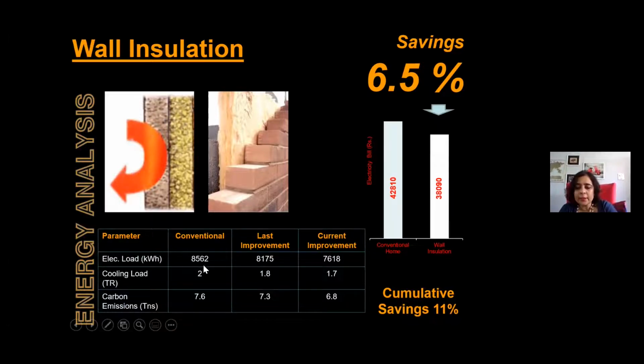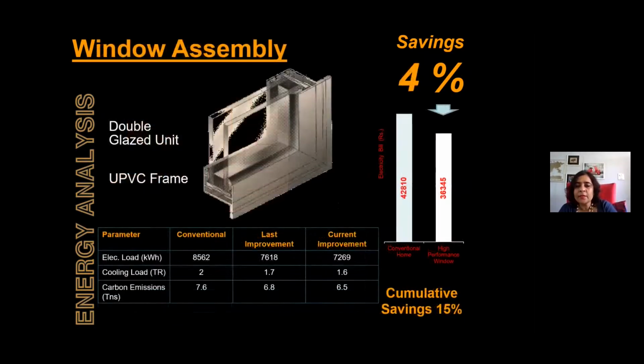We saw that our cooling loads actually dropped from 2 tons to almost 1.7 tons, and so did the electrical loads. Then we used DGU and UPVC frame against aluminium frame. While we did debate using aluminium frame with thermal break, this was giving us slightly better performance at that time, so we went ahead and used UPVC, which helped save another 4% energy.